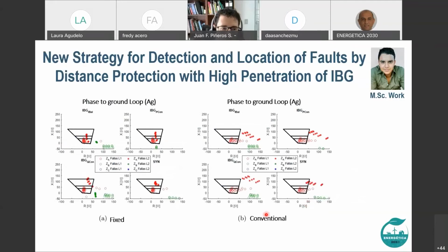And one solution for that, for example: my colleague David, the researcher who spoke before, is working on a new strategy for detection of the location of faults by distance protection with high penetration of IBG. It's important, this work he's doing, because what is the problem? As you can see in this graphic here on the right, there are many failures that we can have in the adjacent lines, the remote adjacent lines. We are not able to see them, or if you have a parallel line, we were not able to see them, because, as I was telling you, we have problems in some zone 2 and zone 3 distance protection backup.